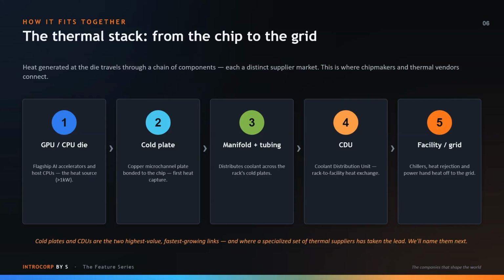It starts at the die, flagship AI silicon, the heat source. That heat hits a cold plate, a copper plate bonded to the chip. From there, manifolds and tubing distribute coolant across the rack. Then the CDU, the coolant distribution unit, exchanges heat between the rack and the facility. Finally, the facility and grid layer: chillers, heat rejection, and power.